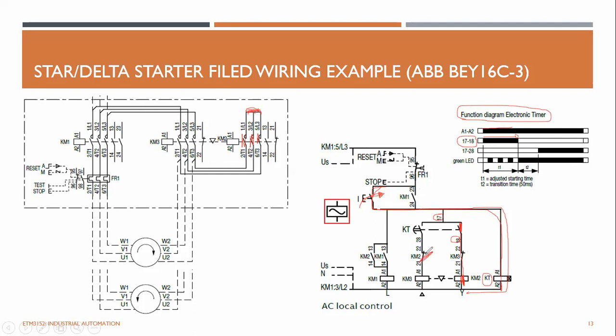Okay, this is opened, and so you can see the KM2 energized, and this is opened, which means the interlock has happened, which means not allowing KM3 to operate at any time. This is opened. At the same time, KM2 is closed, which means this contact will close. So now the current has another direction.